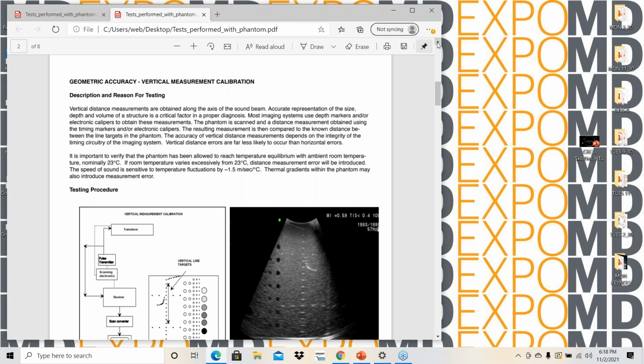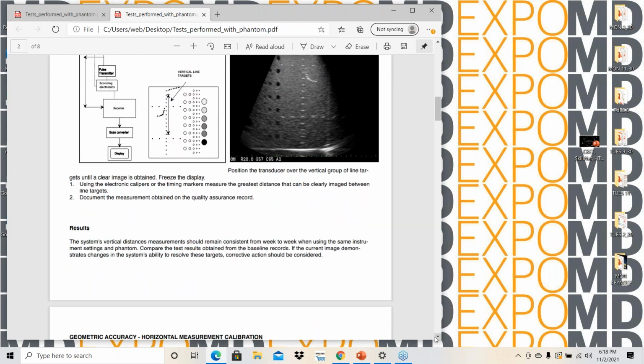So that's axial and lateral. I'm going to skip a little bit, but it tells you the testing procedures at the bottom, and they're exactly the same for axial and lateral, except for the dots you're looking at. I just explained the difference. The dots are top to bottom or left to right. The testing procedure is using the calipers. You measure and see if you can tell the difference, how far the difference is. It's pretty simple, top to bottom, left to right. It's the same procedure for axial and lateral. And then it tells you your results right there, what you should expect.